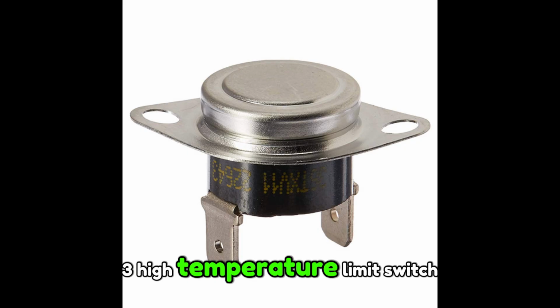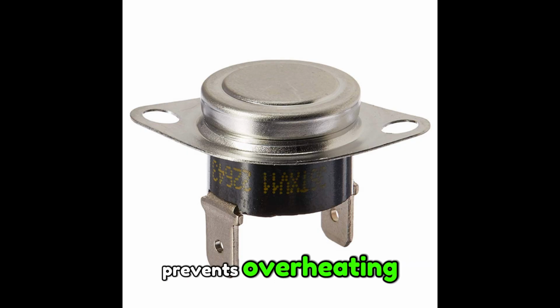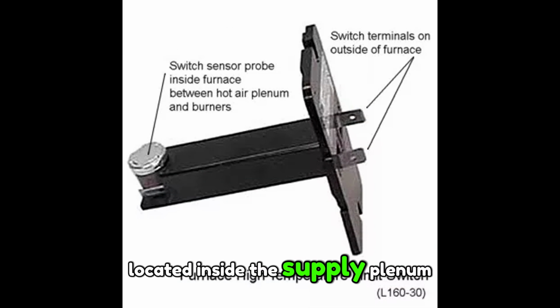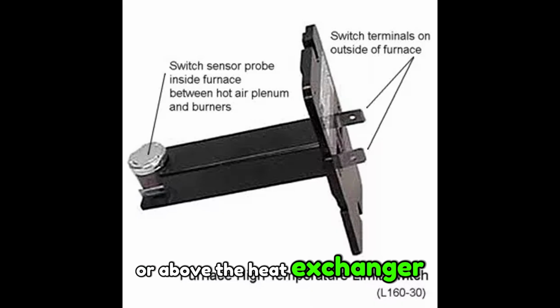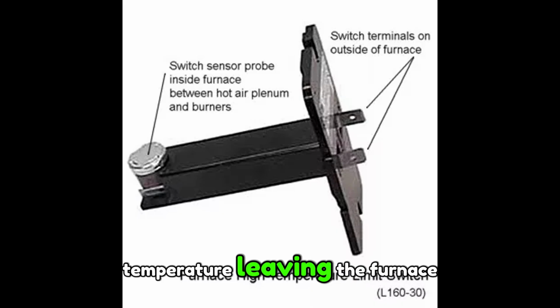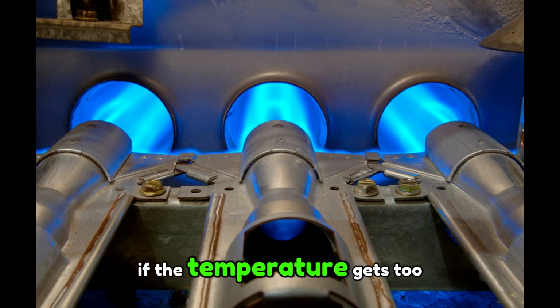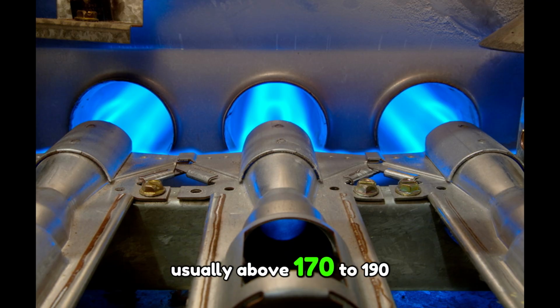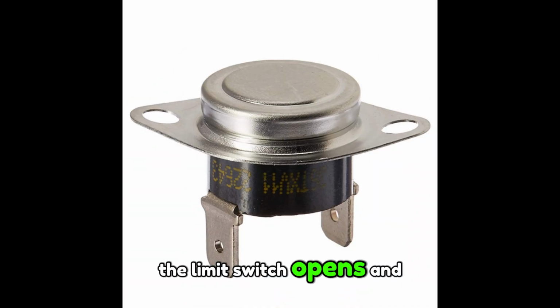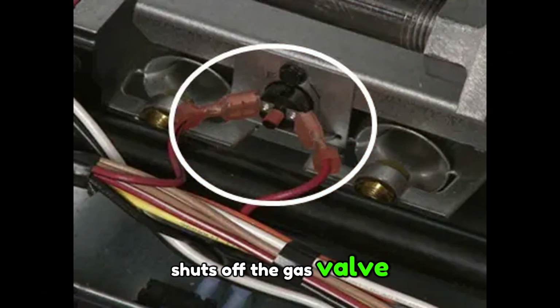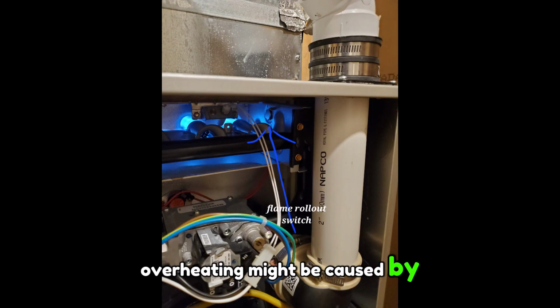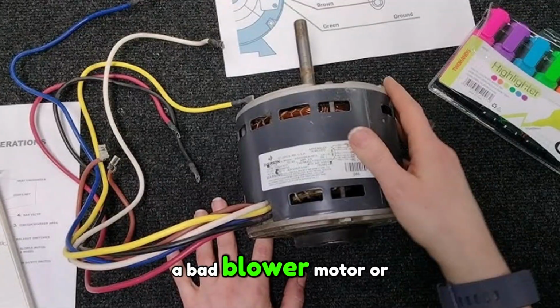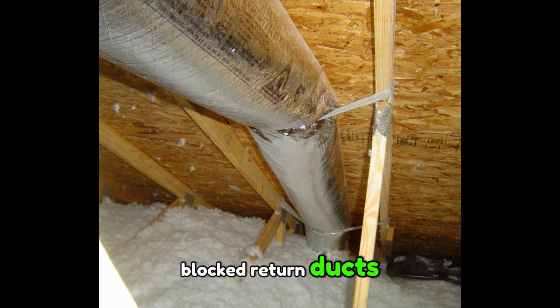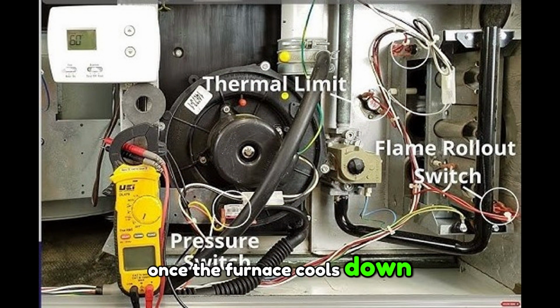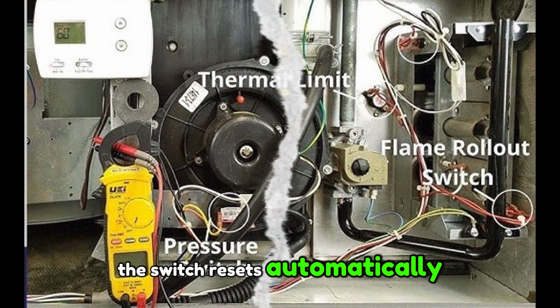3. High temperature limit switch prevents overheating. Located inside the supply plenum or above the heat exchanger, this switch measures the air temperature leaving the furnace. If the temperature gets too hot, usually above 170 to 190 degrees Fahrenheit, the limit switch opens and shuts off the gas valve. Overheating might be caused by a clogged air filter, a bad blower motor, or blocked return ducts. Once the furnace cools down, the switch resets automatically.